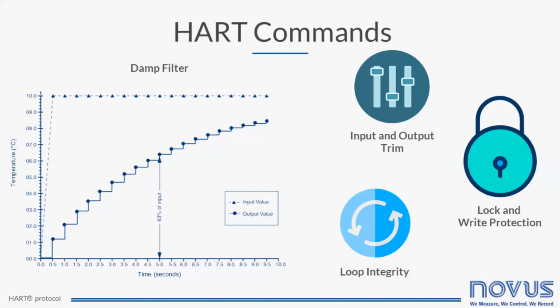DAMP is a filter that changes the transmitter response time to smooth variations in the output rate caused by rapid changes in input. For example, consider a temperature transmitter. If the temperature undergoes a step change from 0 to 10 degrees and the damping is set to 5 seconds, the transmitter calculates and reports a new reading every 500 milliseconds using the damping equation. At 5 seconds, the transmitter output will be 6.3 degrees, or 63% of the input change, and the output continues to approach the input curve according to the filter algorithm.